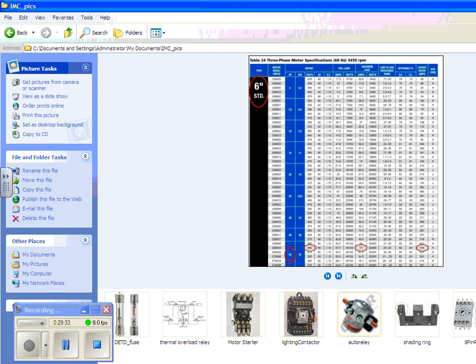Okay? And a lot of times you would think, no, I've got to go up to a size 4. No, that's if it's at 200 volts, like 208. That would not be the right starter if you're operating at 240. So it's very voltage dependent. Why is that? The amount of current that's going in is dependent on the voltage, because the power you're putting in divided by the voltage will be the current, right? So the higher the voltage, the lower the current will be. So you have to take that into consideration when you're selecting these starters.